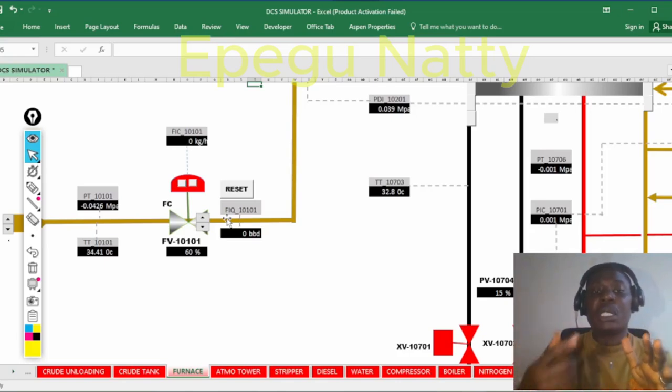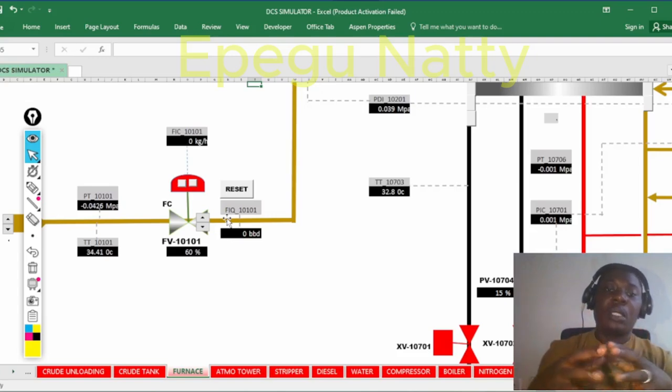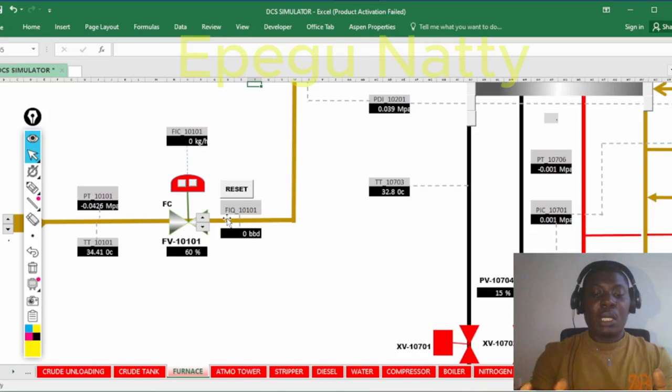Meanwhile, the pump was still running. Nobody noticed, and after an hour, a field operator doing an inspection noticed the pump was very hot. The temperature of the pump was reading around 100 degrees. The casing of the pump was very dark. It was almost like it wanted to explode.